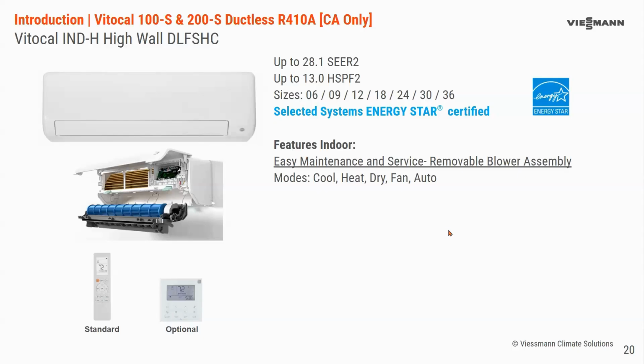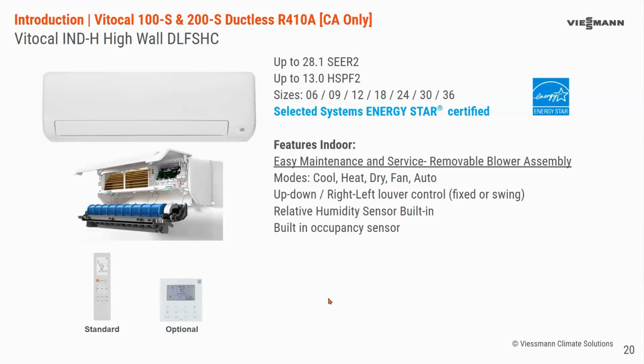Some standard things across all of these indoor units are the modes: cool, dry, heat, fan and auto. So the dry mode is a dehumidification mode, but it is not a replacement for a standalone dehumidifier. It'll allow the remote to have a humidity reading that you can set for the room, and it'll maintain that. You have louver control, up, down, left, right, fix or swing. Again, it has the built-in humidity sensor for that dry mode. There is an occupancy sensor, which is that circle there on the right of the high wall, and that functions a few different ways.